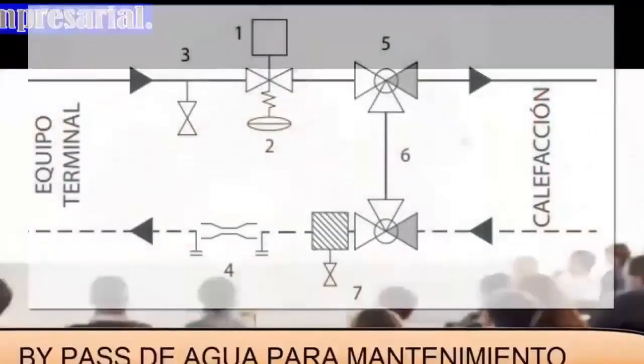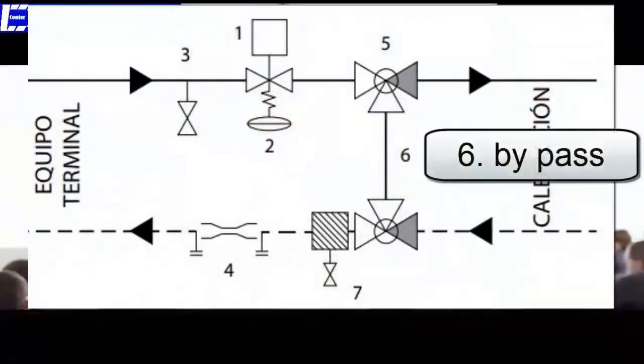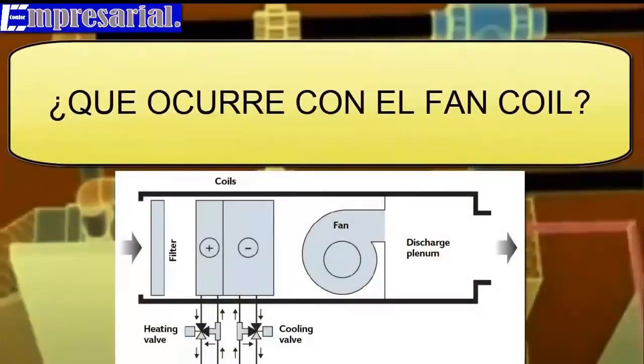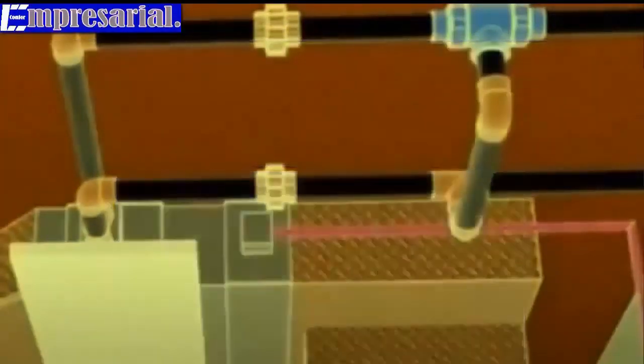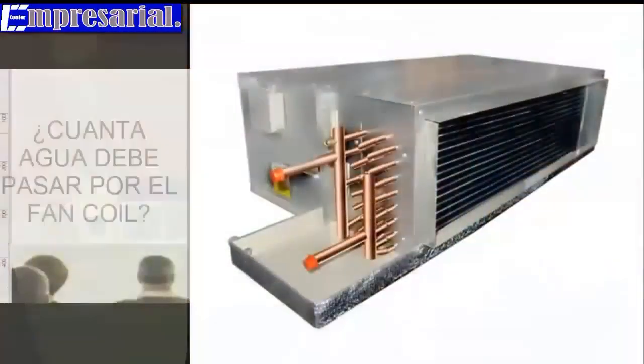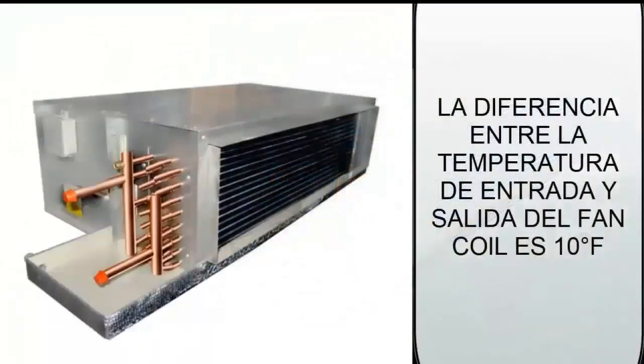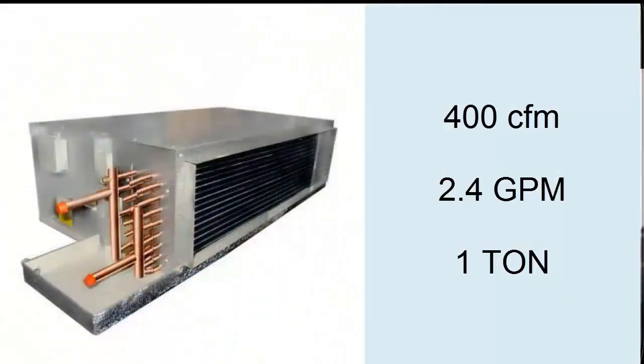Bypass: when the solenoid valve closes, the flow of water which was originally directed towards the exchanger is diverted through this pipe. It is also useful for maintenance. As for the fan coil, we must remember that these units usually work with a variation of water temperature between the outlet and the inlet of 10 degrees Fahrenheit. With these conditions, a fan coil should receive approximately 2.4 gallons per minute for every 400 cubic feet per minute of air that it is conditioning.